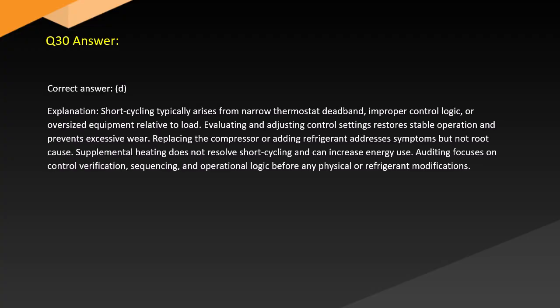Answer. Correct answer. D. Explanation. Short cycling typically arises from narrow thermostat deadband, improper control logic, or oversized equipment relative to load. Evaluating and adjusting control settings restores stable operation and prevents excessive wear. Replacing the compressor or adding refrigerant addresses symptoms but not root cause. Supplemental heating does not resolve short cycling and can increase energy use. Auditing focuses on control verification, sequencing, and operational logic before any physical or refrigerant modifications.